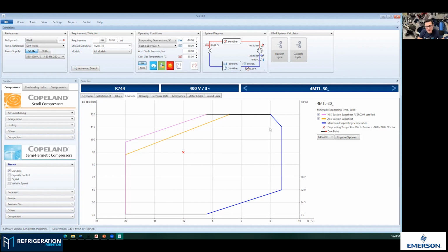I love that you brought that up because I had this when I was running the lab in Emerson, Canada. We set up a cascade system and I had a contractor come in, put the drive on the compressor, set everything up, all great. I didn't think anything of it. And then about 3 or 4 months later, all of a sudden the compressor failed, and we're like, what happened? It's a brand new compressor, brand new drive.